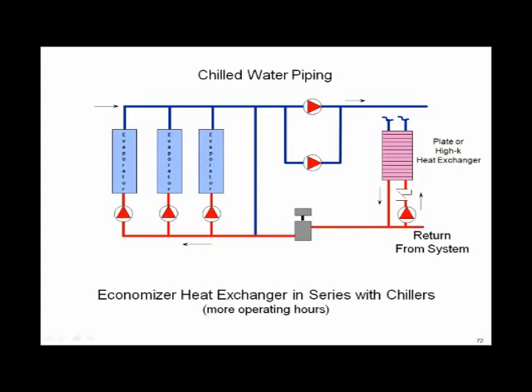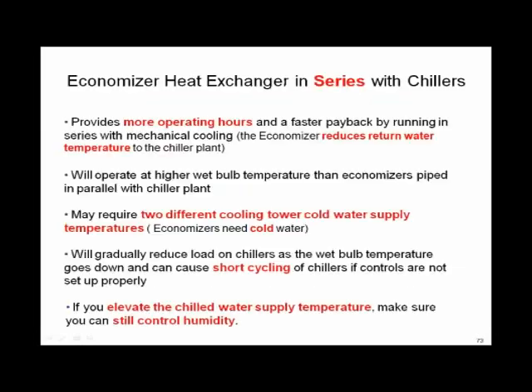So here we go. Now the water side economizer is on the return water side, say the 58 degree return water. And I want to subcool that 58 degree water a little bit with my water side economizer before it gets to the chiller plant, before it gets back. Then my chillers are going to finish it off and make it 45. In other words, now I can turn the water side economizer on earlier, get more operating hours, and get a lot more payback than I could any other way. Let's take a little closer look at this as we go.